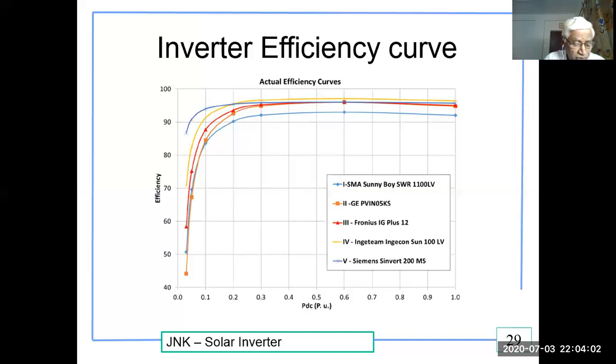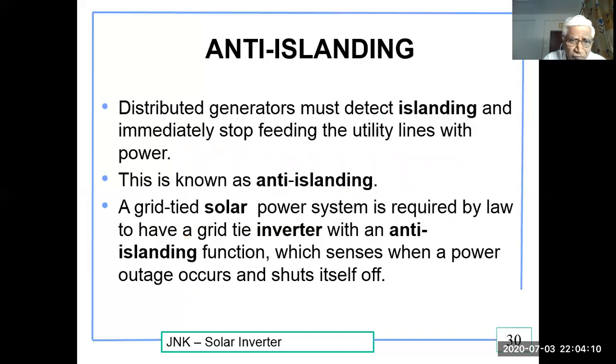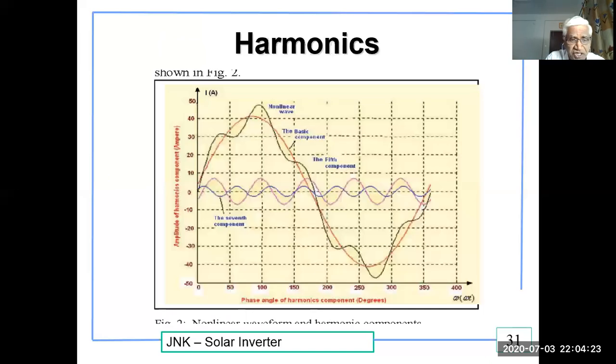Grid-tied inverters are expected to have active islanding detection capacity. Now, what is islanding and what is anti-islanding? Islanding refers to the situation in which the inverter in a grid-tied setup continues to power the system even though power from the grid operator has been restricted due to safety issues.